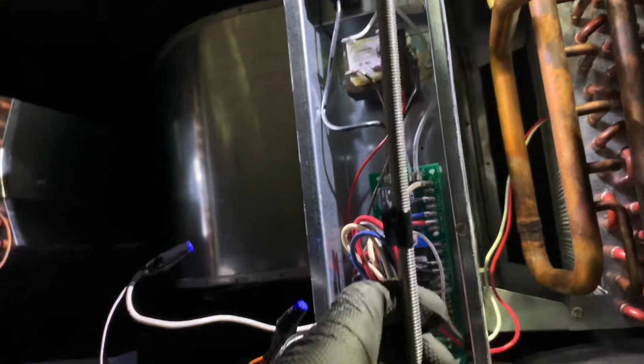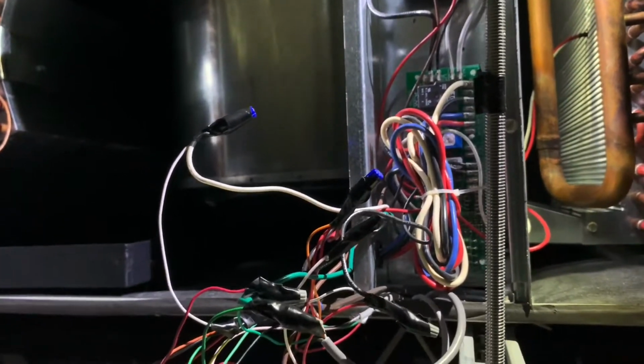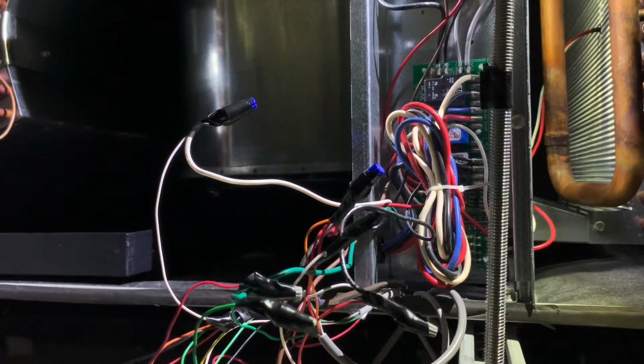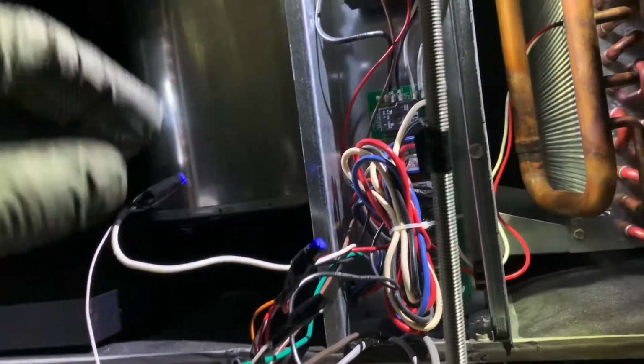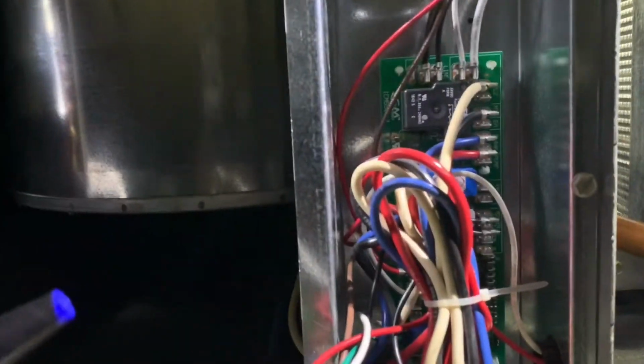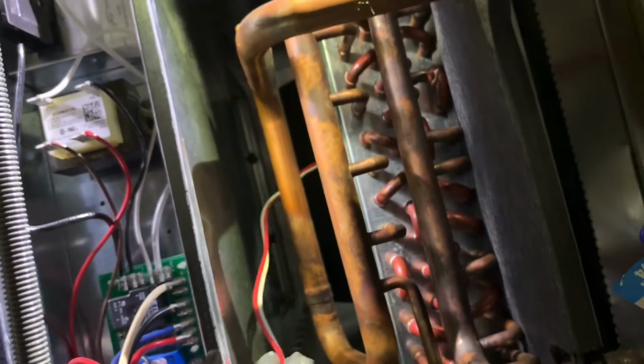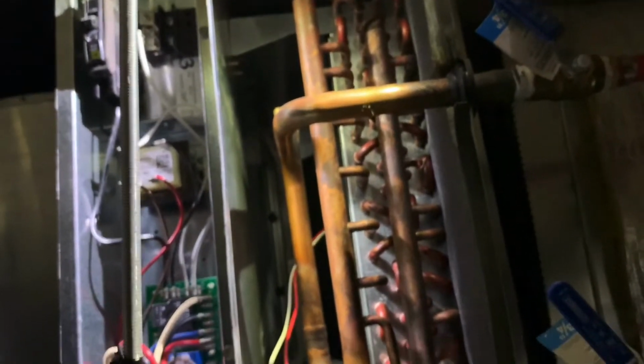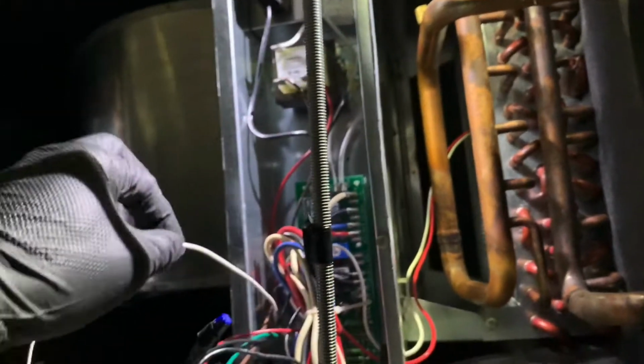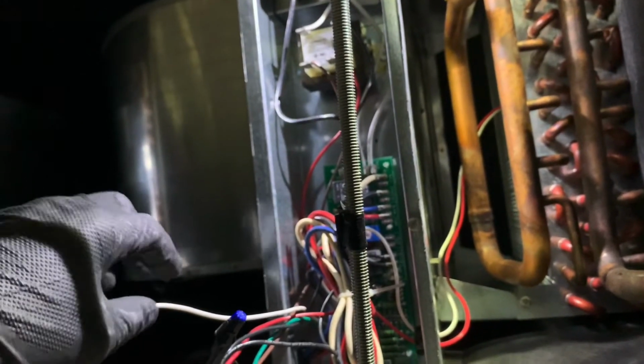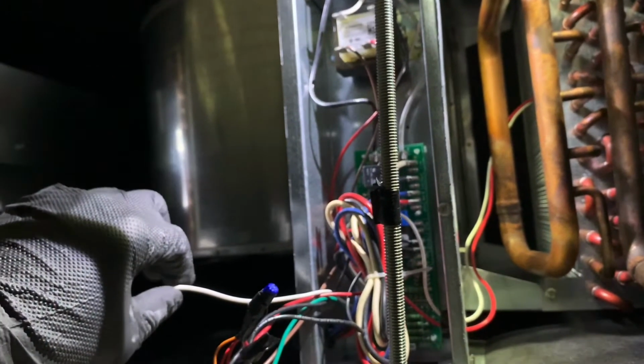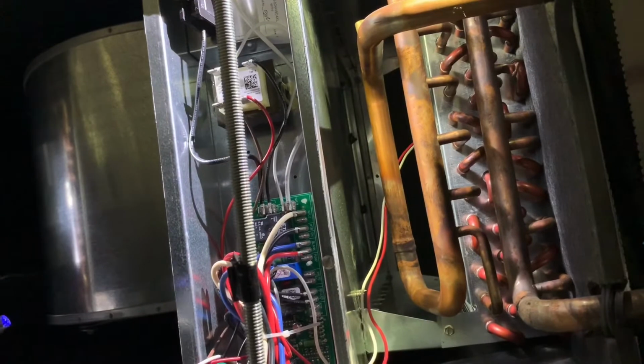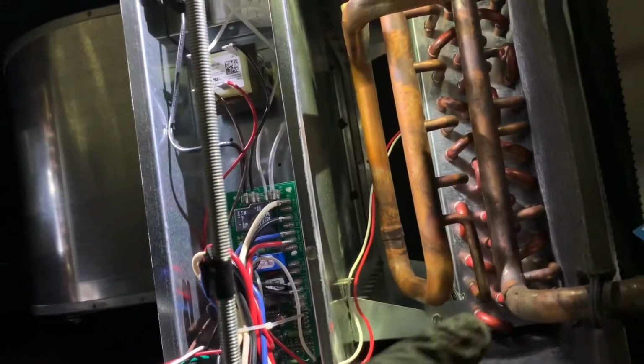Now this air handler, once you call for heating, once 24 volts goes into that white wire, the thermostat is in heating, it's going to activate. There's relays on the board, and there's also a thermistor that's already factory installed into the hot water coil. And so once you call for heat, it basically will delay the fan, make the fan ready, wait for the coil to be hot, sensing with the thermistor, so it knows when the coil is hot. And so it won't turn the fan on when you call for heat unless the coil is hot.